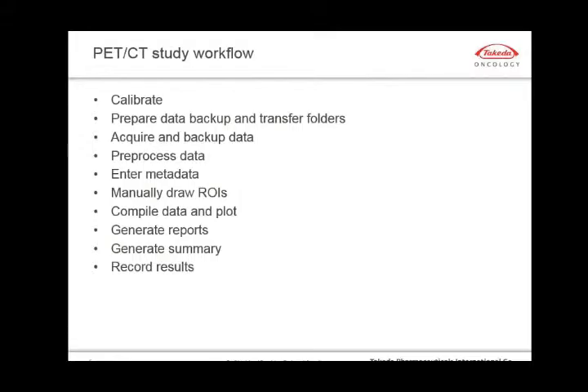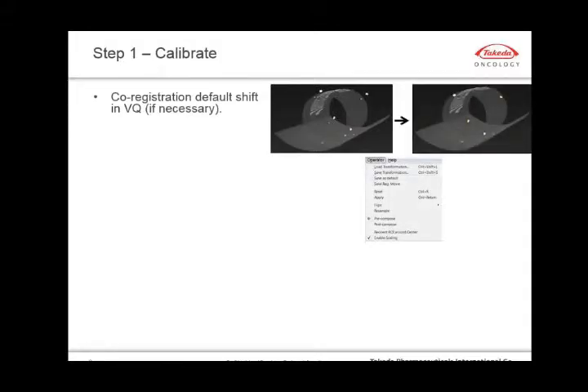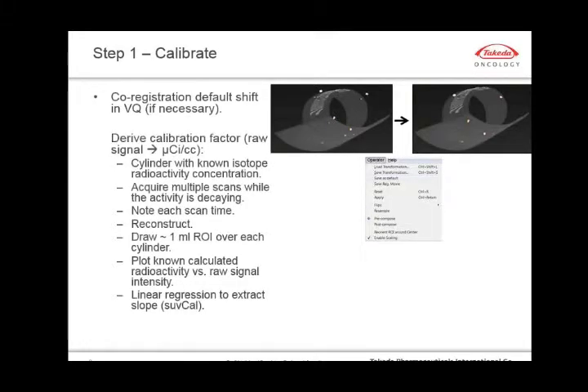That's where VivoQuant and IPACS come into play. I'll now run through our typical standard PET-CT study workflow, which consists of approximately ten steps. The first step, which takes place even before we plan a study, is that we calibrate our scanner. We do two types of calibration, the first being a co-registration. For that, we take a short PET-CT acquisition of a cylinder containing four radioactive point sources, load the reconstructed data in VivoQuant, co-register both images manually, and save this transformation as a default shift.